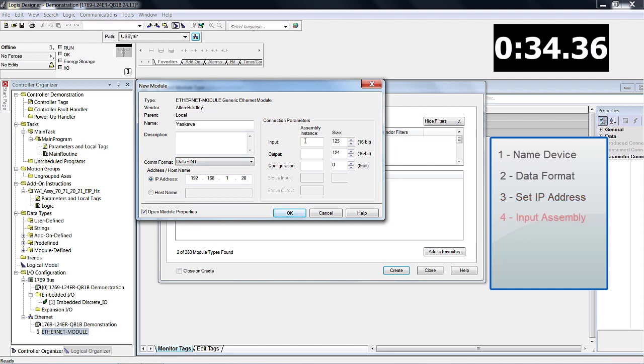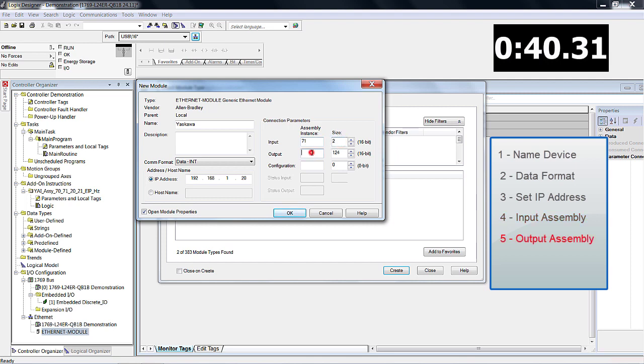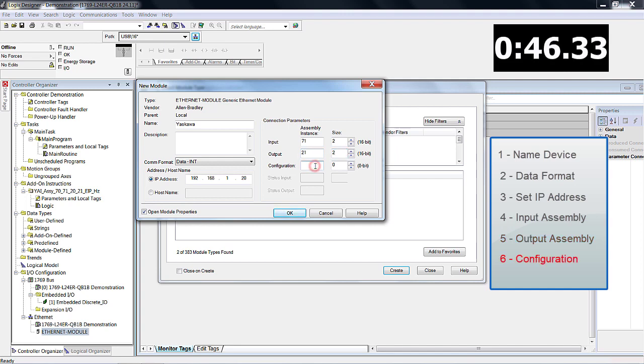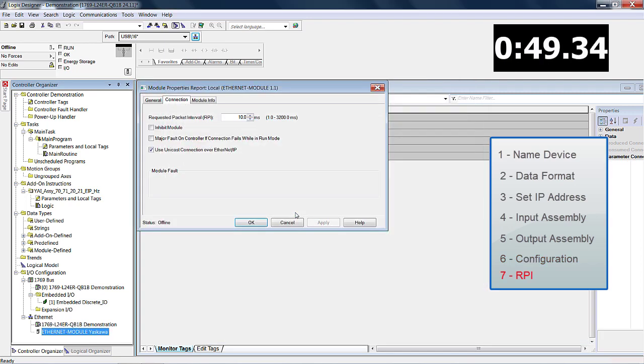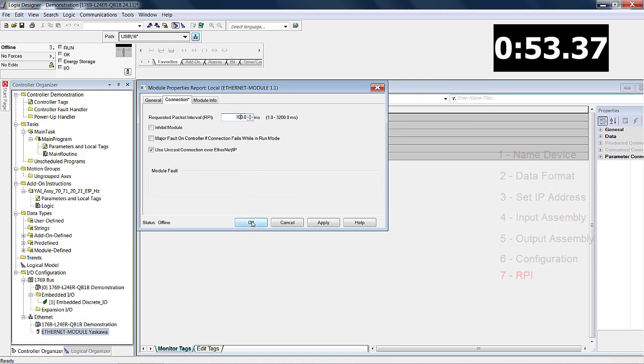Step 4: set the input assembly to 71, which is 4 bytes or 2 words. Step 5: set the output assembly to 21, which is also 4 bytes or 2 words. Step 6: set the configuration number to 1 with a size of 0. The final step is to set the RPI time to a recommended 100 milliseconds.